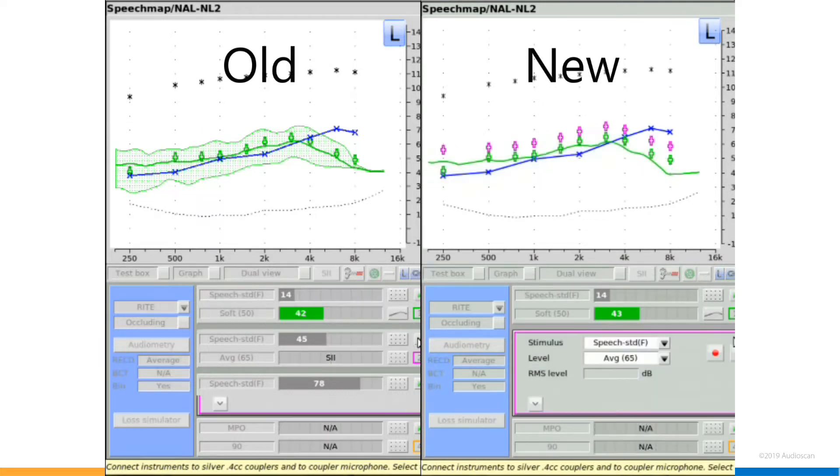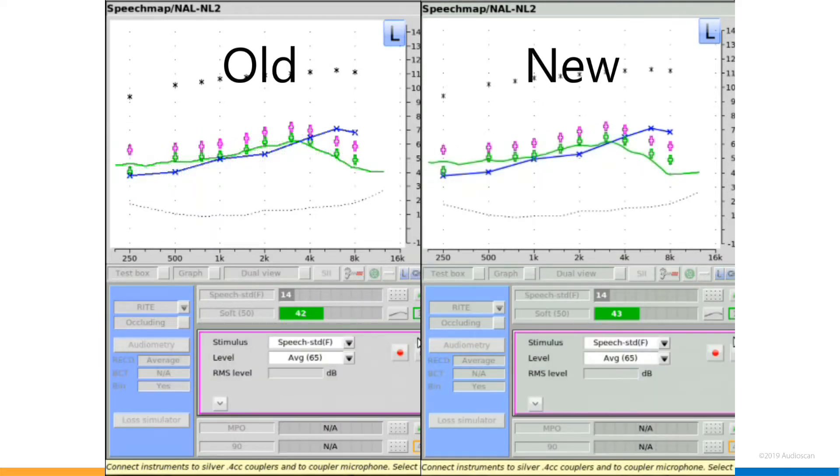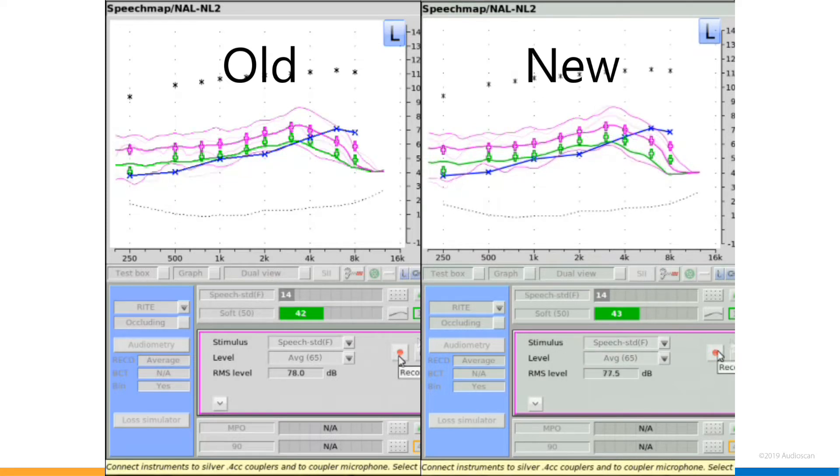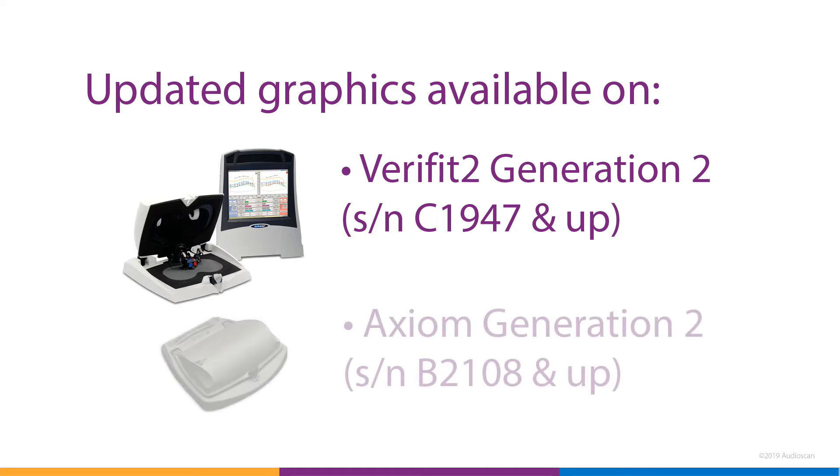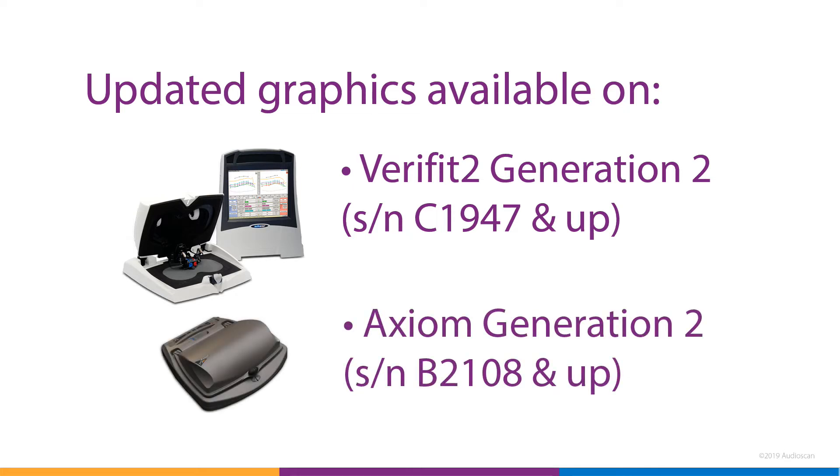2019.2 software has also brought changes to the look of our test graphs. The new high definition graphics allow for smoother curves and true transparent colors. Due to hardware limitations, this particular feature will apply only to Verifit2 Generation 2, which is serial number C-1947 and up, and Axiom Generation 2, which is serial number B-2108 and up.